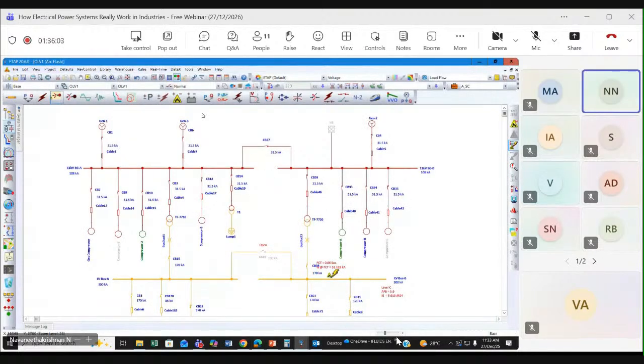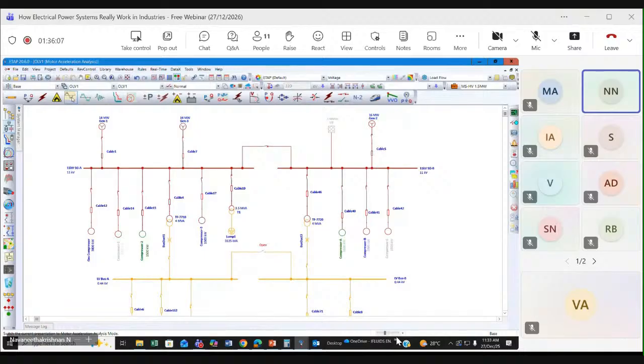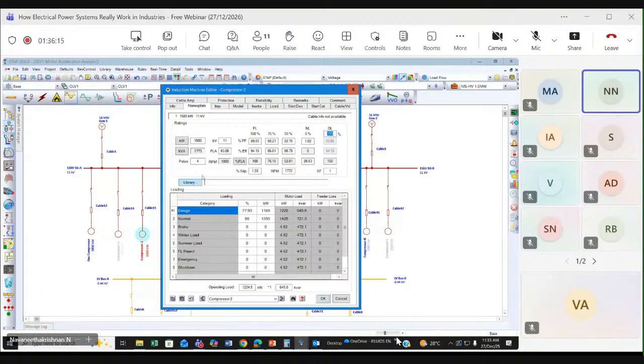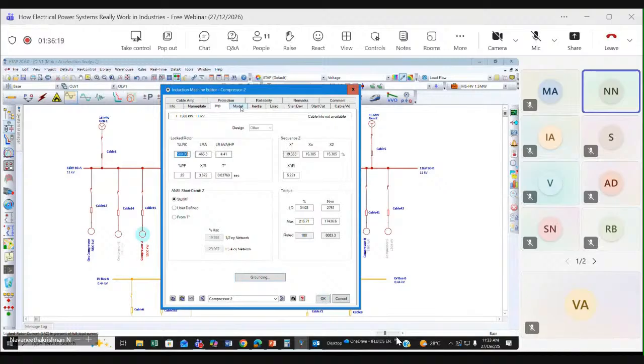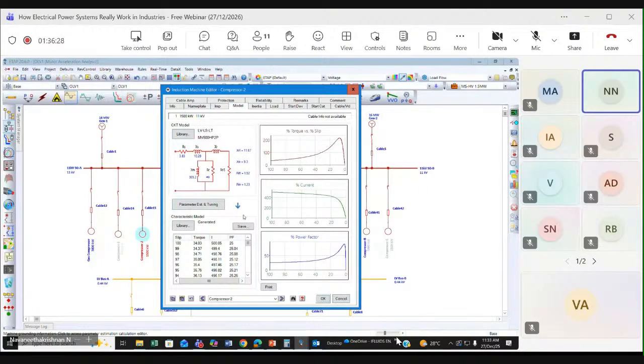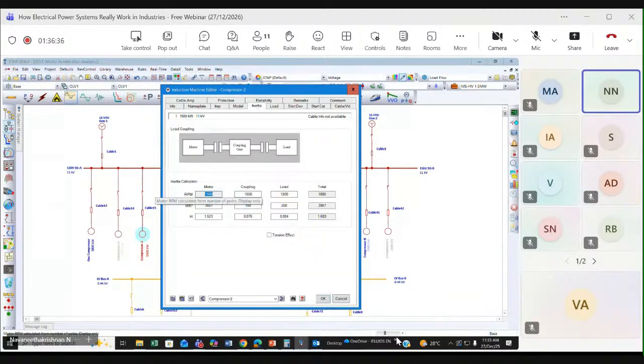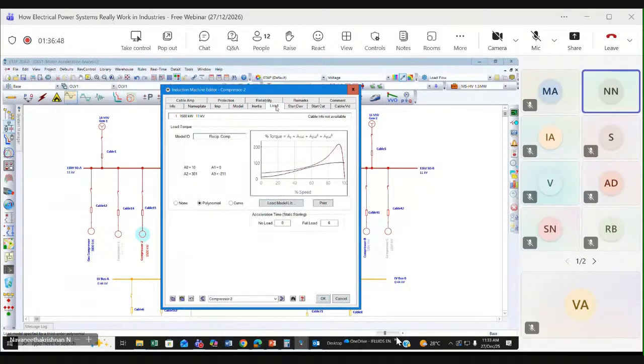So we'll go now to some other models, like motor acceleration. For example, nameplate details are given, and we have selected the impedance model. You have to get that data sheet, model it here, and then specify. You have to get the inertia of the load. Plus, you can do the motor starting study. So you can see the load curve. This is the load coupled, for example, a compressor. Torque curve. Okay, here itself you can find it very easily.